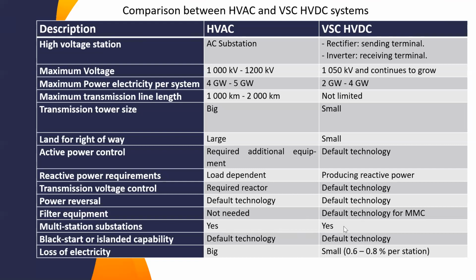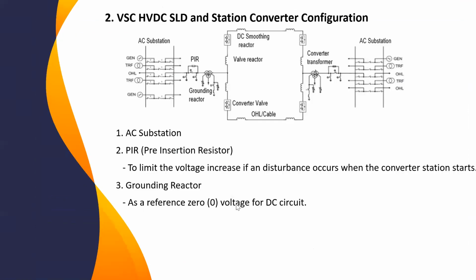Multi-station, both for AC and VSC, we can. And black start for AC, the default technology works in case our generator is equipped with black start capability. If not, it will not be working. However, for VSC, by default, we can do a black start capability. In terms of losses, AC will be big because we have more number of cables. But here we have a small number of cables, so that's why the losses will be small.